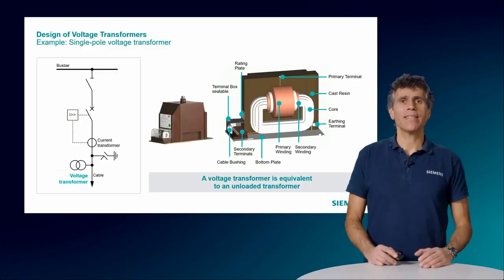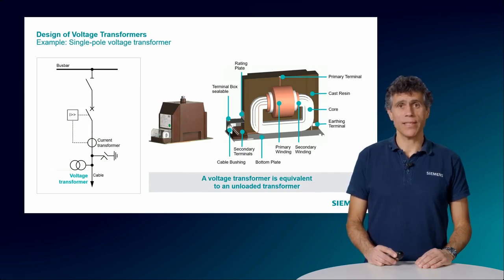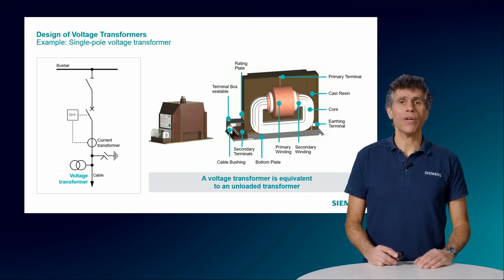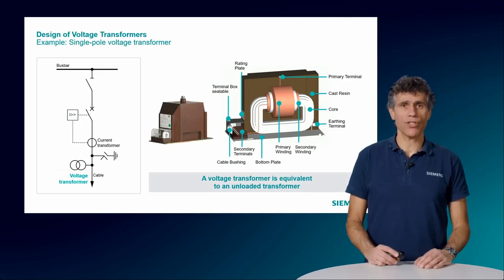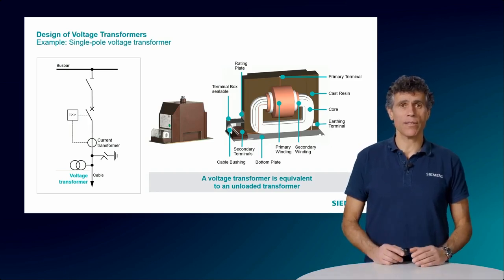The winding is designed to withstand the mechanical and thermal stresses of the operating environment. Similar to the tapping of CTs, it's also possible to incorporate taps for adjusting the voltage output as needed. The transformer core is usually made from high-grade, grain-oriented silicon steel and is responsible for focusing the magnetic field generated by the primary winding, allowing efficient transfer of energy to the secondary winding. The core's design and material are vital for achieving high accuracy and minimal energy losses.